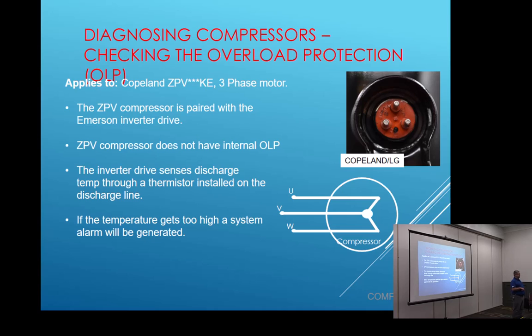On these variable speed compressors, anything with an inverter drive, if you get an inverter fault, you still want to verify the compressor is good by ohms. You want to check it across each leg and to ground, because the inverter driven systems are so smart, it doesn't allow that breaker to trip. I can tell you, I've never seen one of these trip a breaker, and have replaced a few of them from grounded compressors, but they never trip the breaker because that inverter is so smart and so fast, it doesn't allow it to even trip. It knows it's bad already.